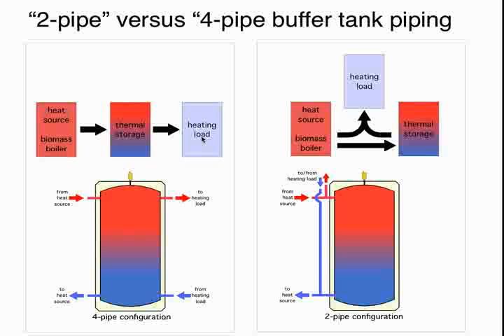Now, in a two-pipe configuration, we have a different situation here. You notice that in a two-pipe configuration, we only have two pipes that directly connect to the tank. We've got one going in upper sidewall, another one coming out lower sidewall, and then we have two T's that are fairly close to the tank, and that is an important detail. For hydraulic separation, we want to keep this T here in the red line as well as this T down here in the blue line. We're going to keep those close to the tank. We want to have minimal pressure drop from that T down through the tank and back to this lower T. But you can see the difference here is the load takes off before the tank.